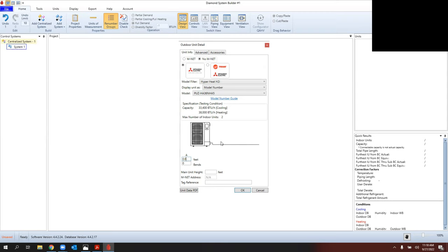I'll select that condenser. You'll see a field for pipe distance — I can enter it here or when I add the indoor unit. For a P Series one-to-one, let's say 30 feet of line set with a couple of hard 90s. If you have a long sweeping 90, you don't enter it, but if you have a hard 90 — like a Zoom-Lock fitting — you would enter that as a bend. Main unit height is the condenser off the ground; for a Hyper Heat heat pump it should be a positive number, ideally off the ground.